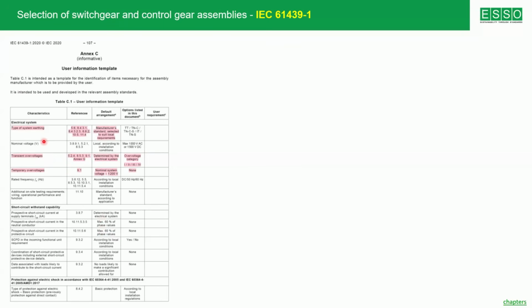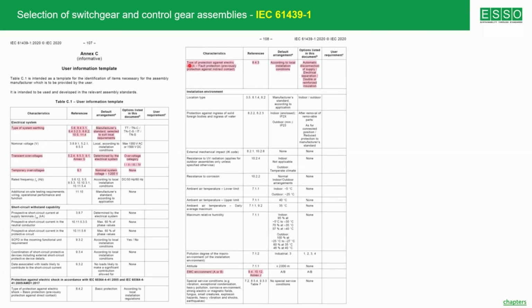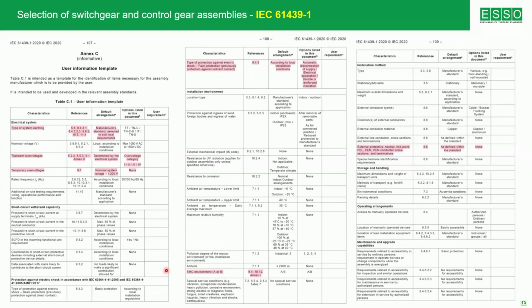And the subjects related to earthing are type of system earthing, transient overvoltage, temporary overvoltage, type of protection against electric shock, what kind of fault protection you are going to make, what kind of EMC requirements are there. Please note, the consultant is supposed to fill up this entire requirement, out of which few are related to earthing. See here, user requirement. The user should define what exactly you are going to do with this panel board and what kind of requirements are there. I just highlighted the requirement of earthing alone.